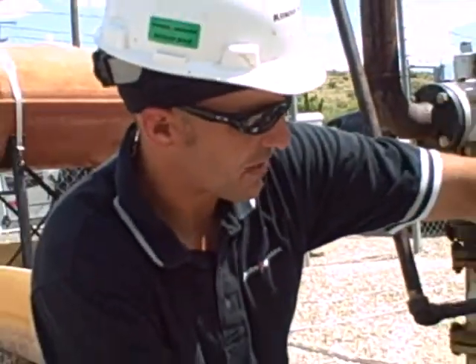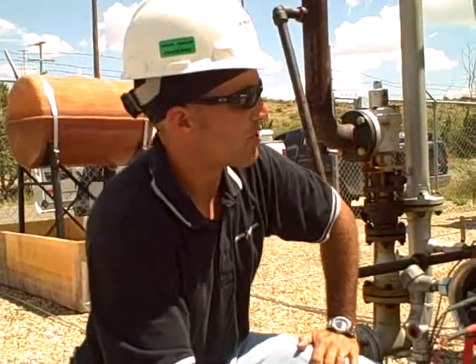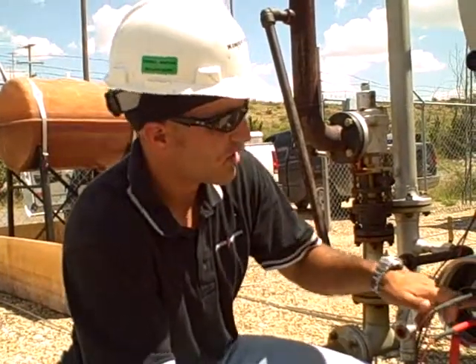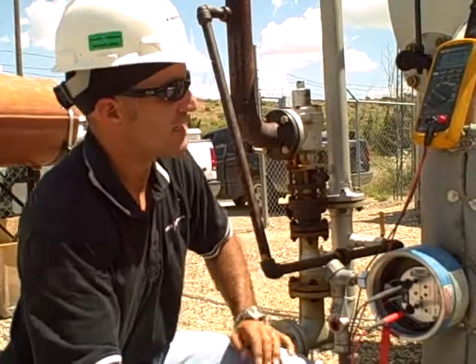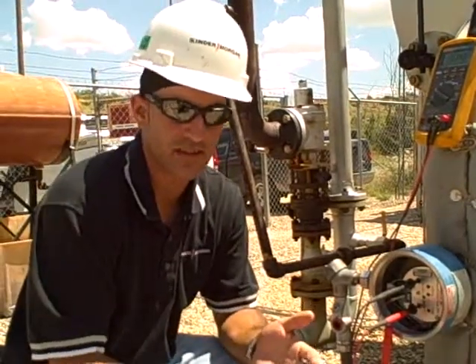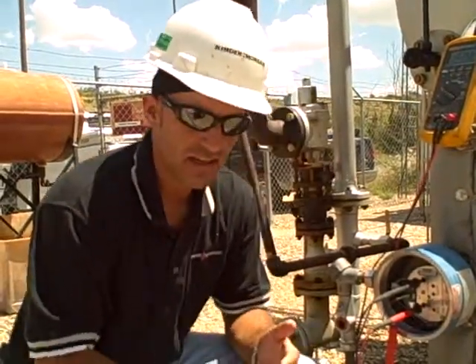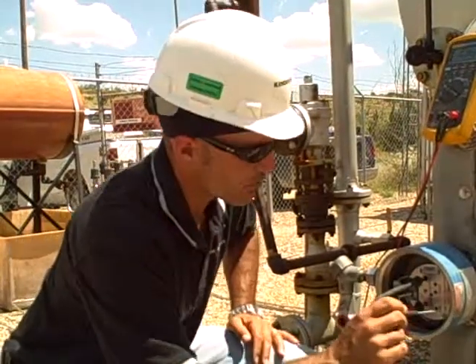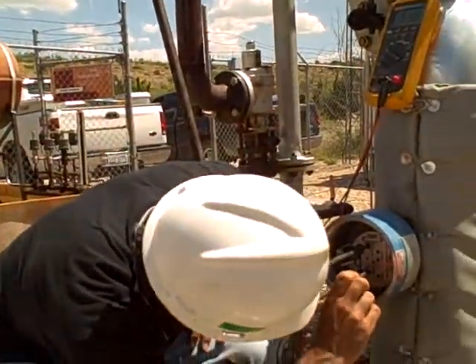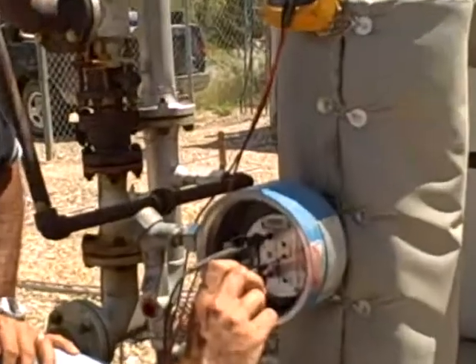Alright, I got a 5.06. That would be plus or minus 3%. Now I'm going to go back to probe. I need to go back to probe and redo my 0 on my voltage, because when you set the output span, it changes your reference point. So I'll go back here and adjust that a little bit.